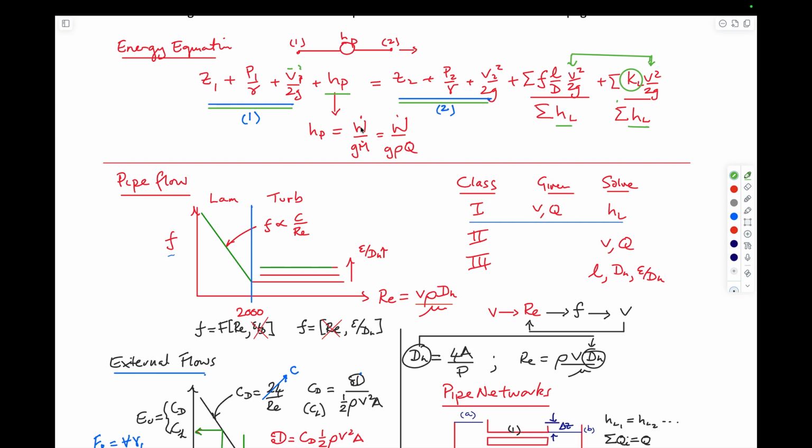The pump head is given by the power divided by the mass rate and acceleration due to gravity, where the mass rate is the volumetric flow rate times density. Together those are kilograms per second, and allow you to calculate power. If you rearrange the equations in terms of upstream and downstream pressure heads, then that typically constitutes the head loss across the system between upstream and downstream if you draw it between two big containers.